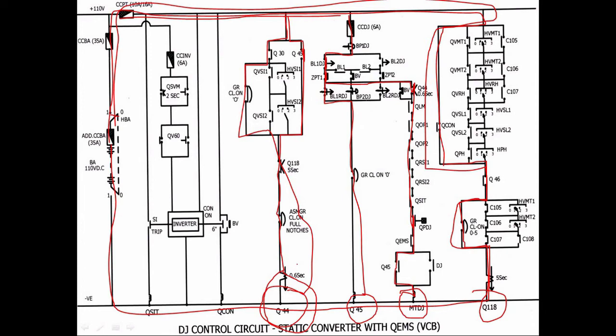Now MTDJ branch gets supply from battery, additional CCBA, CCBA, CCPT, CCDJ, BP1DJ normally closed interlock, BLDJ closed, ZPT is kept on 1, Q44 NO interlock closed, all safety relays de-energized condition, QEMS not in energized condition, and since already DJ is closed, here DJ normally open interlock closes. Already previously it is closed, supply will come via DJ normally open interlock. That means after closing of DJ, Q44 gets supply from a different path and MTDJ branch gets supply from the DJ NO interlock.